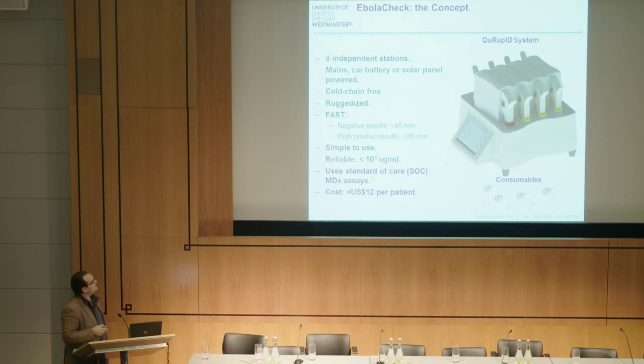Eight independently operating power stations. It runs on a car battery or a solar panel. All the reagents here are freeze-dried, so it's cold chain free. It's ruggedized. It gives you a negative result in under 40 minutes and a high positive in under 20. It's simple to use. We'll see what that means. And it's reliable. It has a detection target of less than 10 to the 4 viral genomes per mil. And we achieve that by putting in it the standard of care molecular diagnostic assays.